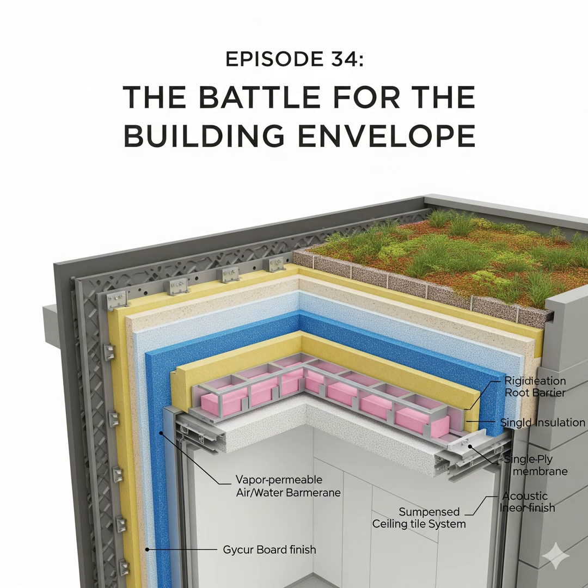Lstiburek really hammers on the importance of air leakage testing, not just for the walls and roof, but for ductwork too. Because air doesn't just move because the wind blows, there's this thing called stack action or stack effect. Warm air inside a building is buoyant, it wants to rise. So in winter it pushes out at the top of the building and creates negative pressure lower down, sucking cold air in through any little cracks or gaps, like a chimney effect. And mechanical systems, furnaces, air conditioners, exhaust fans, they move air around too, creating pressure differences. Leaky ductwork is a huge culprit.